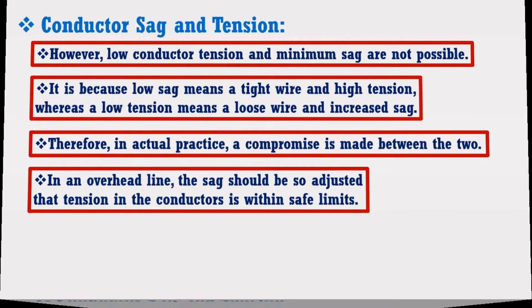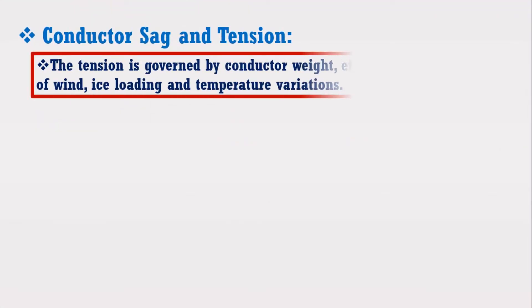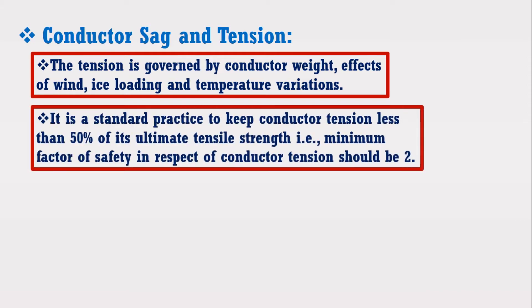The tension is governed by the conductor weight, effects of wind, ice loading, and temperature variations. It is a standard practice to keep the conductor tension less than 50% of its ultimate tensile strength, meaning that the minimum factor of safety in respect of conductor tension should be 2.